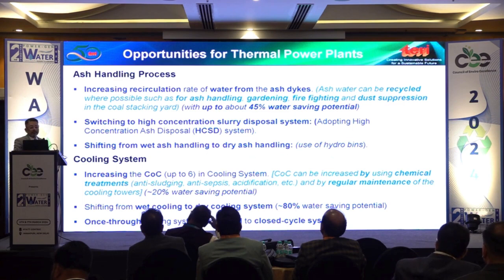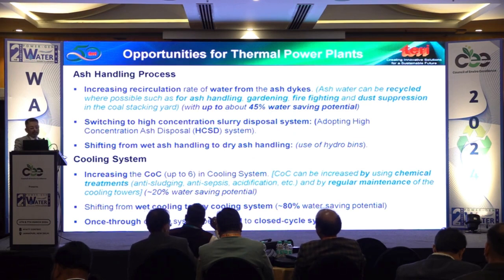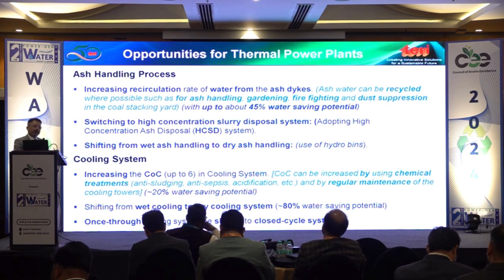The other option is to move from wet ash handling to dry ash handling - for example, NTPC Dadri was already doing that, among a few other examples. Also, switching to a high concentration slurry disposal system, where you maintain a better ash-to-water ratio, can significantly reduce water consumption. These interventions are already being taken up across the world and can be adopted to significantly reduce water use in ash handling.